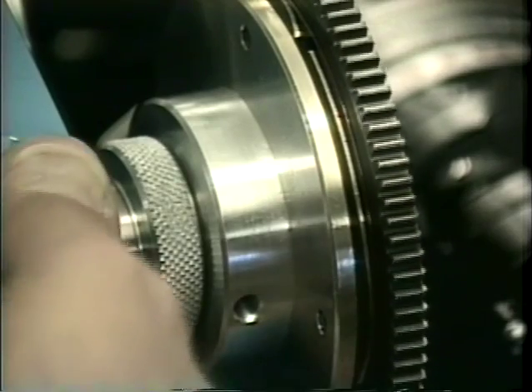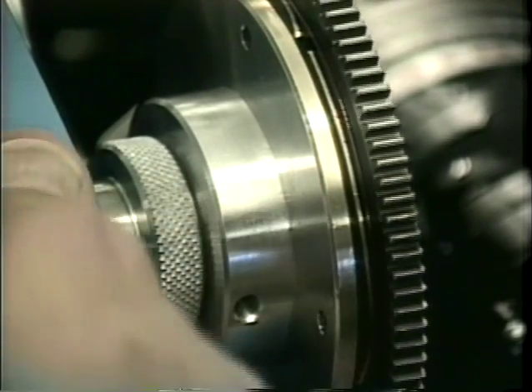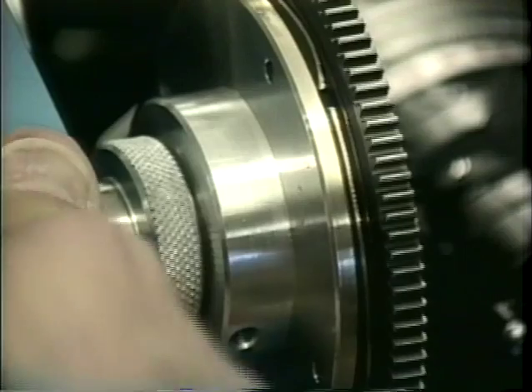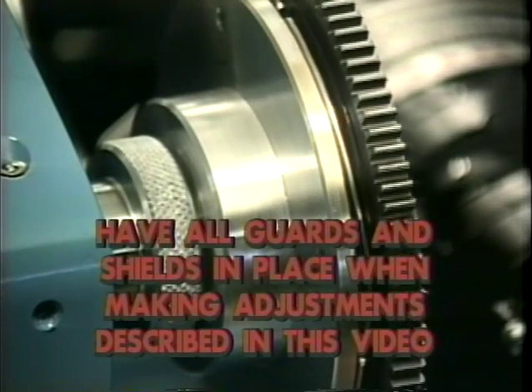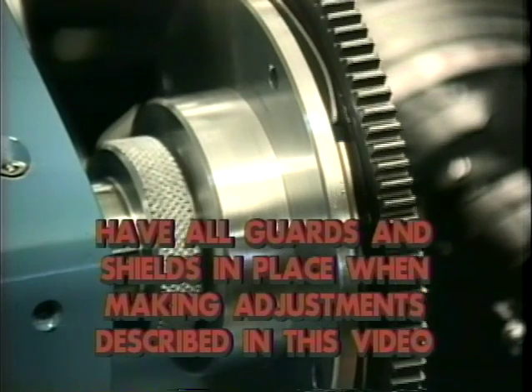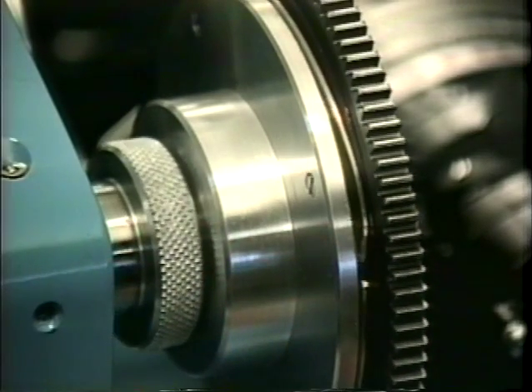Here we're increasing the drive power or torque by rotating this adjusting collar counterclockwise as looking from the front of the machine. There we've got it. Adjust it until it just begins to drive and then give it a half a turn more.